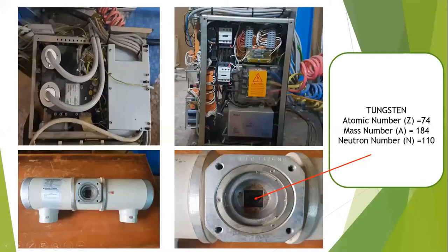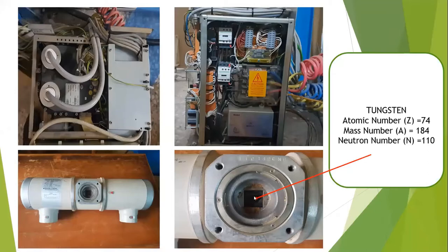These are our anode and cathode on the transformer — a step-up transformer. In my country we operate on 230 volts, and we want to raise this to about 150,000 volts — quite remarkable. Here we can see an x-ray tube. The tungsten target is very close — since we're dealing with very short wavelength, the anode and cathode are close together. Electrons move from the cathode filament towards the tungsten anode.